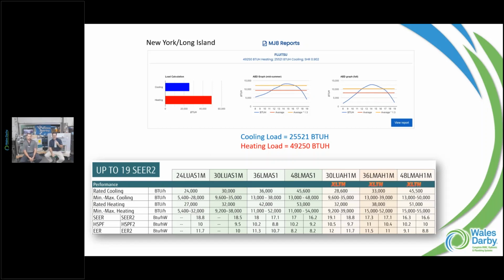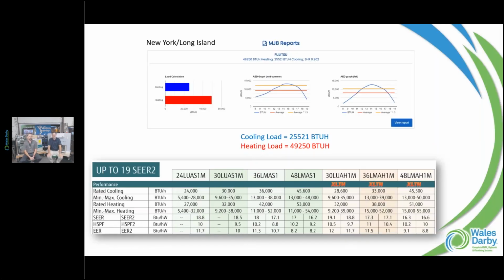So just looking at this heating load, for 49,250 BTUs, you look at some of these numbers down below here, and I'm going to go to the 4-ton, just because that's where it would point me - 49,000 BTUs. You can see I've got a rated number down here of 53,000 BTUs. I've got, let's say, a minimum and max from 11,000 up to 54,000. So if I'm sizing out of the catalog and taking my heat load and saying, alright, that's going to be my machine because I can do up to 54,000 BTUs - we've got to be careful.